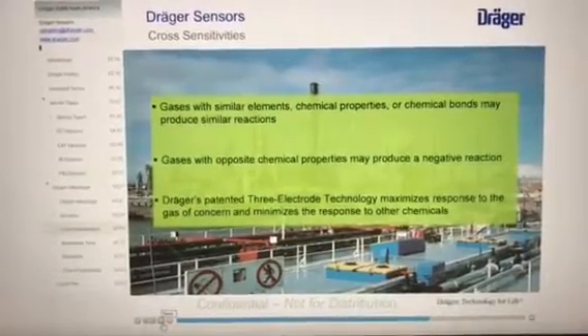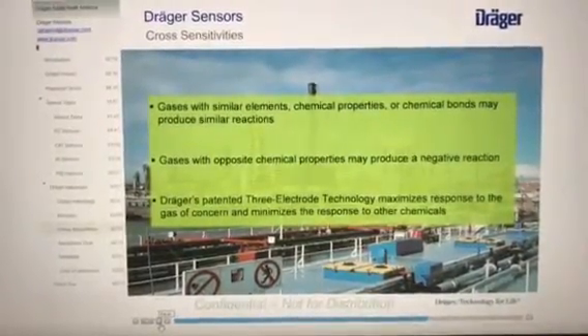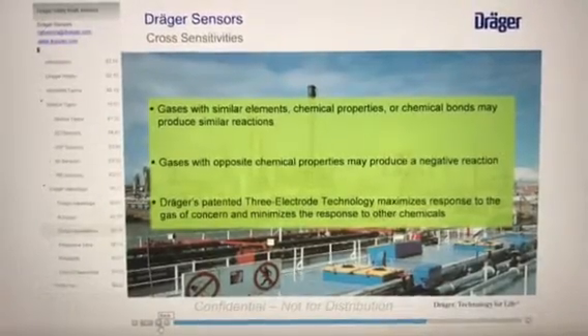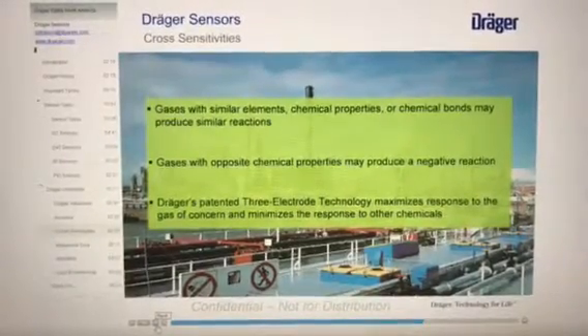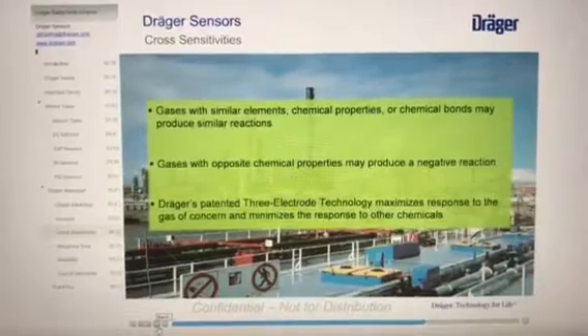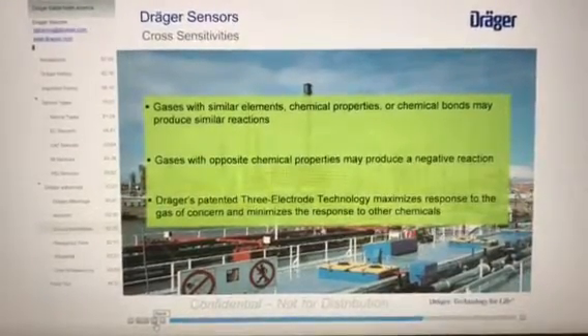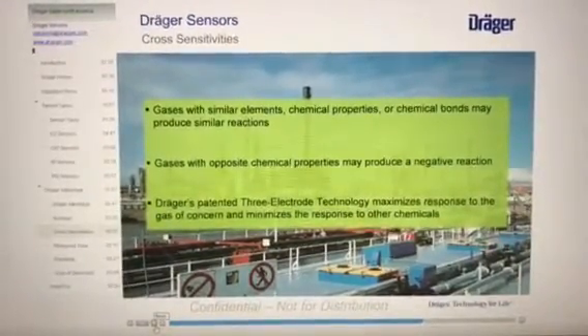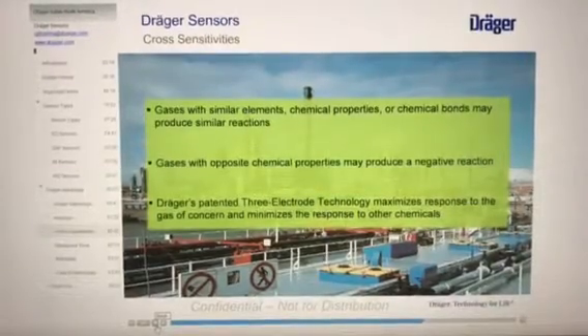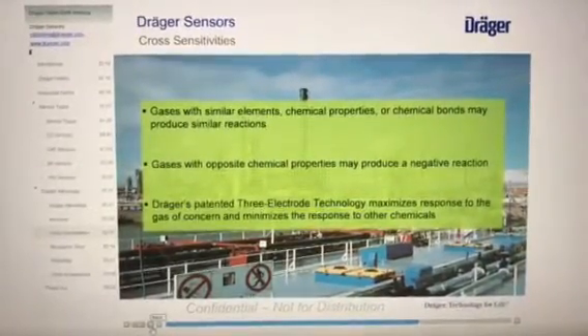Cross-sensitivities can also be found with gases that have opposite chemical properties to the target gas. These may produce a negative reaction, leading you to believe that calibration wasn't done in fresh air, and that your calibration was incorrect. Draeger sensors have some of the lowest cross-sensitivities on the market.